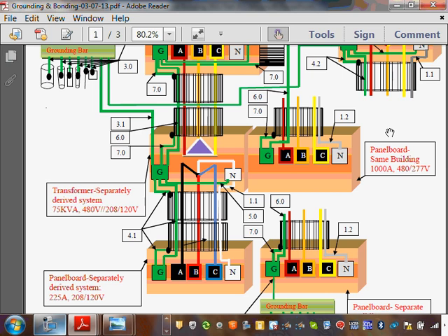Would the system work if we bond? I'm a devil's advocate here. I do a lot of things, that's what I did when I was young. Yeah. I always say, guys, in order for the power system to work, all you need is a hot on a grounded system. Take a hot conductor, go to your backyard, and drive a rod or some metallic object in the ground, and tie the hot to one side of the lamp or bulb. The other side, take the ground, and the light will go bright. So you're using Mother Earth as a neutral, not even as equipment ground, against the code, but it works.